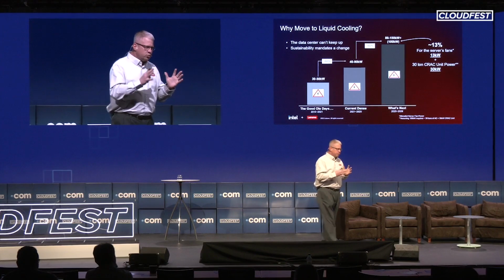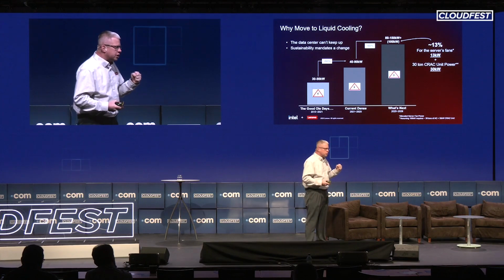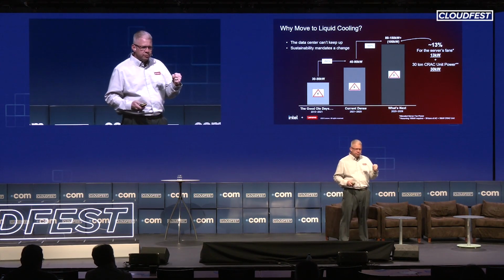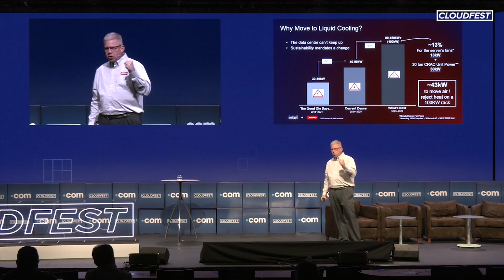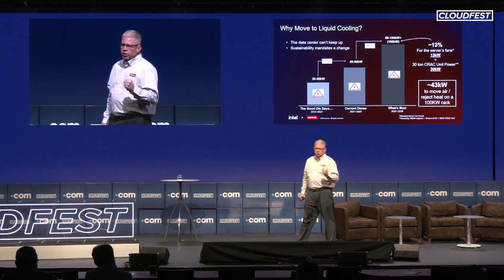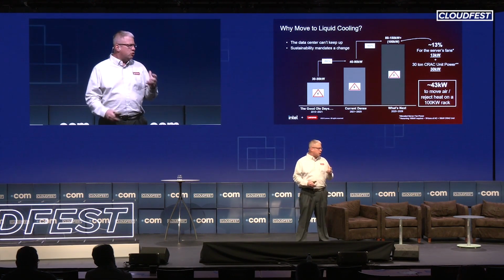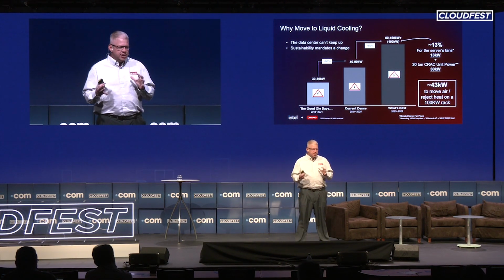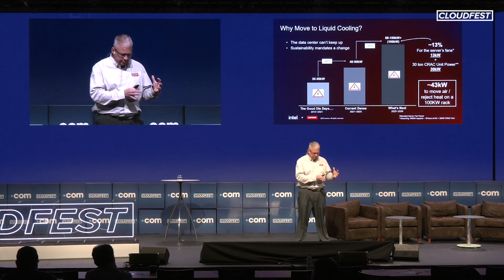Now that's one piece of it. What a lot of folks don't think about is the actual piece that takes that hot air removed from the server, and what do you do with it? It's about 30 kilowatts to actually remove that heat out of the data center on a typical CRAC unit that you'd have in the data center. So you very quickly get to a point where you're at 43 kilowatts just to remove heat from that single rack.